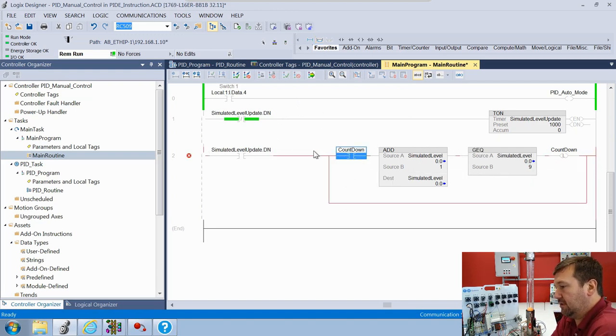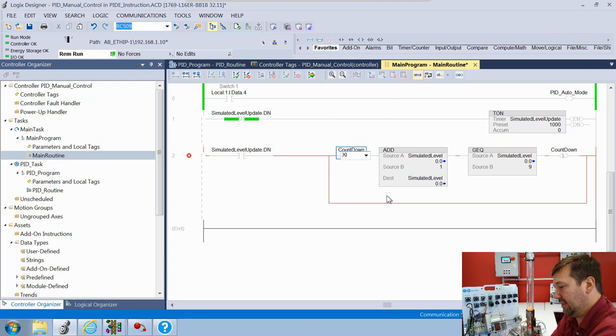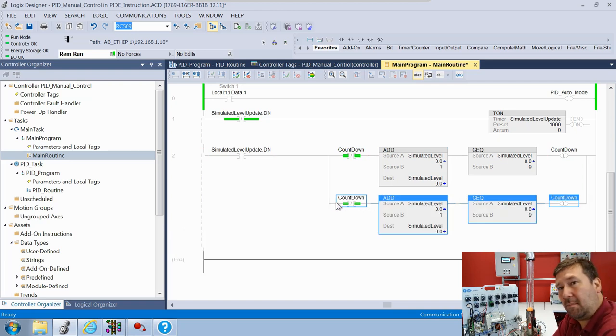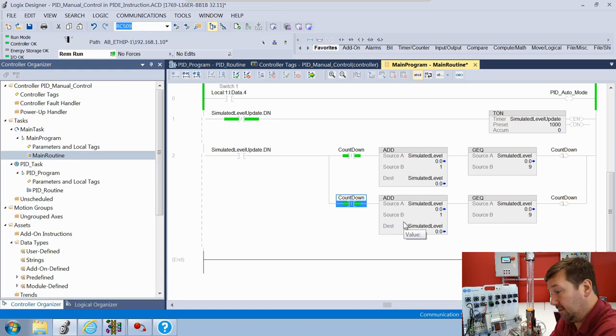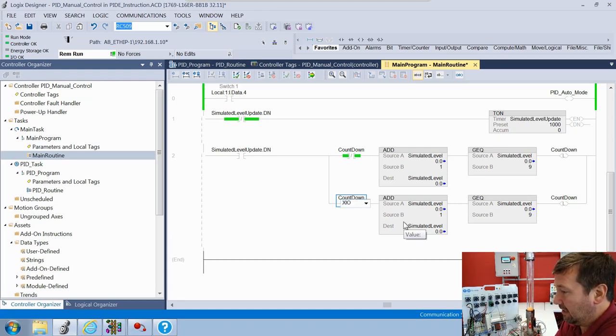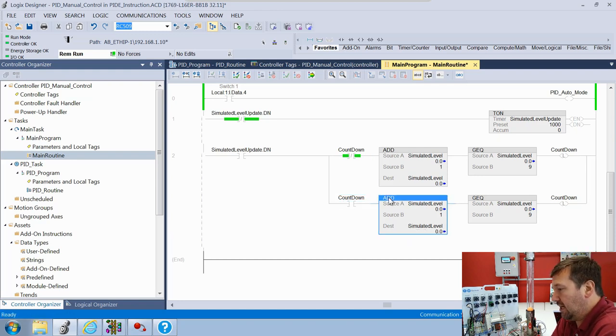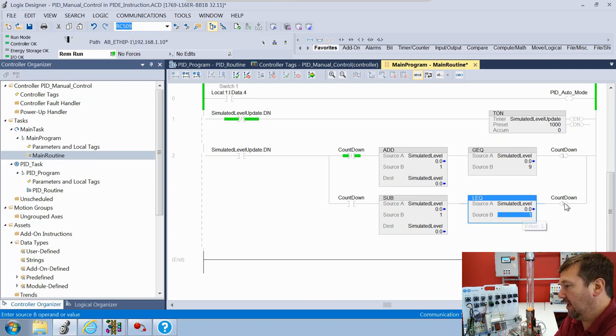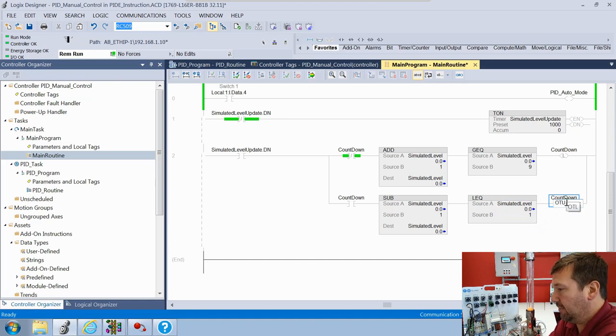Now let's make a branch around this. I made a mistake - that first countdown should be an examine-off, not an examine-on. Highlight the instruction and hit enter to change the XIC to an XIO. Now let's highlight those four instructions, copy them, click the lower branch and paste them. On the lower branch we change the countdown back to XIC, change ADD to SUB for subtract, change greater-than-or-equal-to to less-than-or-equal-to checking for one, and instead of latching that bit we're going to unlatch it.